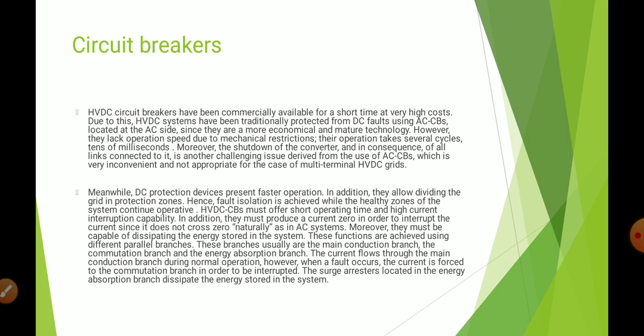HVDC circuit breakers must offer both fast operating time and high current interruption capability. In addition, they produce a current zero in order to interrupt the current, since it does not cross zero naturally as in AC systems. Moreover, they must be capable of dissipating the energy stored in the system. These functions are achieved using different parallel branches. These branches usually are the main conduction branch, the commutation branch, and the energy absorption branch. The current flows through the main conduction branch during normal operation. However, when a fault occurs, the current is forced to the commutation branch in order to be interrupted. The surge arresters located in the energy absorption branch dissipate the energy stored in the system.